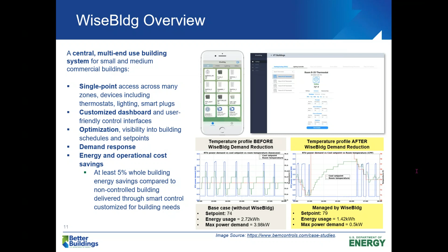The lower right plots show a particular system case study that BEM Controls provided, linked at the bottom of the slide. It's a building that needed help mitigating peak demand costs. By widening the thermostat set points, they let the room temperature ride over so compressor cycling wasn't causing peak demand, lowering power demand from 4 kilowatts down to 0.5 kilowatt. Some pretty neat stuff there.